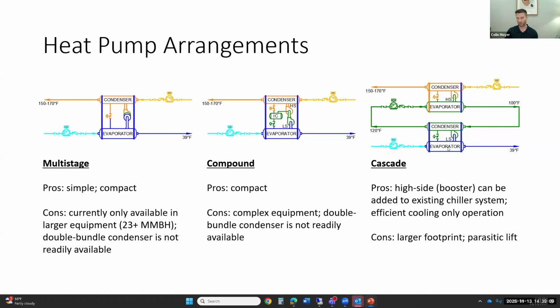So if you want to make more chilled water than the relative amount of hot water that would be produced, you can connect towers or other heat rejection equipment into the intermediate loop. And then you can do pretty efficient cooling operation for that excess cooling load that you don't need to recover in the spring and summer months.